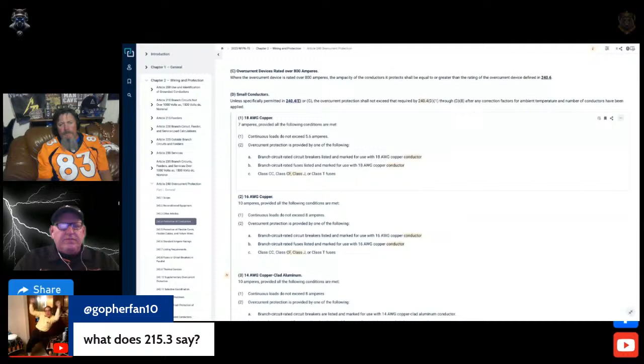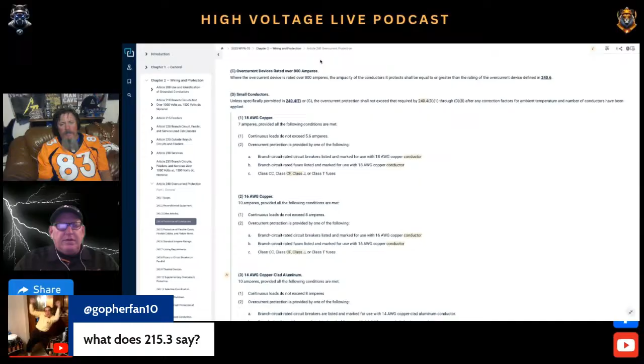Right. Okay. So I come back here, I look at Article 240, and I pick up 240.4(C). Was that 215.3 you just read? Yeah. So we have 15 comments, 20 comments in here saying, what does 215.3 say? 215.3 says go back to 240. And it says, where the overcurrent device is rated over 800 amps, the ampacity of the conductors it protects shall be equal to or greater than the rating of the overcurrent device. If I take 4 230 amps, parallel it 4 times, that's 920 amps. That's sizing your conductors based on the load. And then once you base it off the load, you're allowed to go down. It literally says it right there. And the next size below that would be 900. You've got the conductors there.